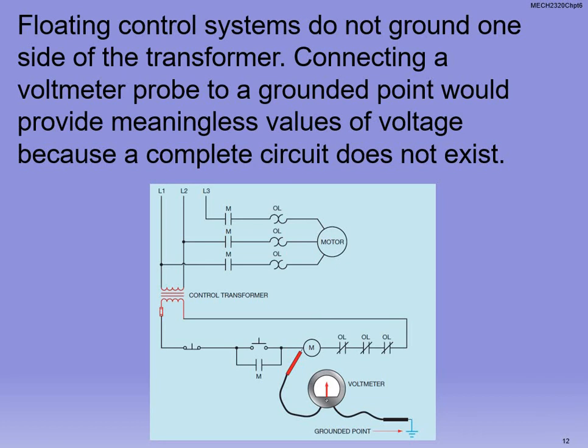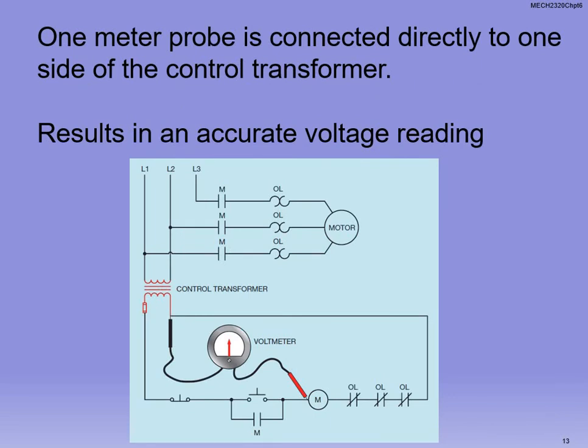They're not necessarily real readings, nor accurate whatsoever, because it's not on the same system essentially. So we call this float grounds when we make this kind of connection. But for us in industry here, it's not necessarily going to give us an accurate reading because the control transformer is not grounded. Okay, the best way for us to get an accurate reading here is to read as we are here, from the motor to the ground side of the control transformer. Even though this transformer is not grounded here, all right, it's just the neutral side that's completing the path. So you would have to make this reading across the motor to get the accurate voltage drop. So hopefully you understand the difference.